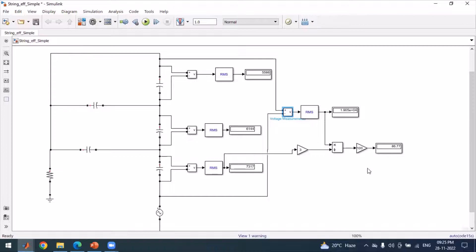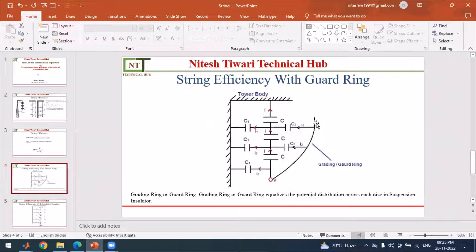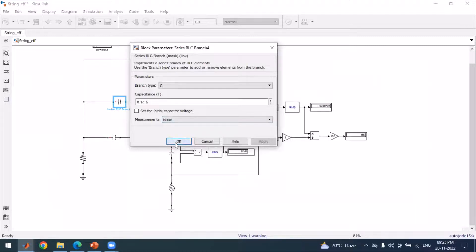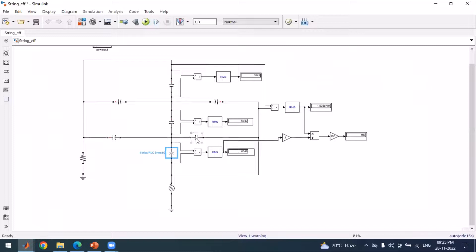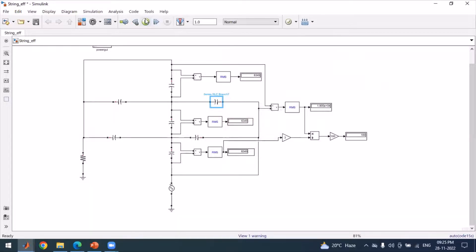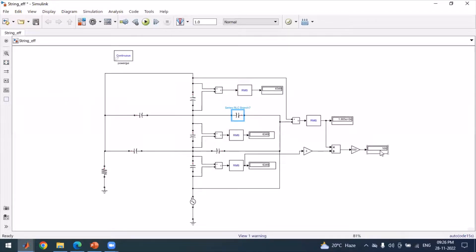To achieve uniform voltage distribution, we can use guarding by connecting additional capacitances. All original values remain the same; the only difference is that we connect two guard ring capacitances — one of 0.2 e-6 and another of 0.05 e-6. After computing the model with these two capacitances added, the efficiency becomes 100 percent.